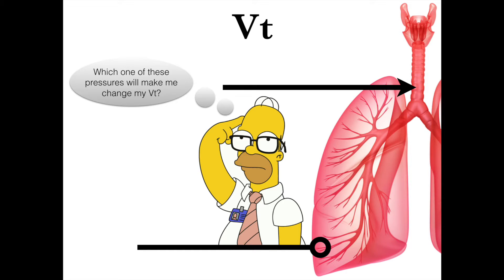We're going to look at two different pressures and the difference between them. The upper pressure is our P-peak pressure, and that's the one that represents the pressure in our large airways. Stuff that can cause that to alarm includes if the patient coughs, if our I-time is set too quickly, or maybe if the sedation is poor and the patient is bucking the vent — that can cause the P-peak to alarm.